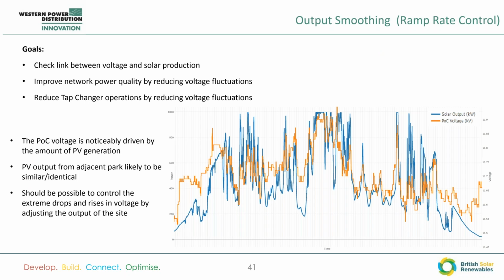Final use case, output smoothing, ramp rate control. So we found that the voltage does fluctuate in line with solar production. Again, we're assuming that the PV production from Higher Hill is likely to be very similar in terms of percentage to what it was at Copley Woods, because they're literally in the same place. So you can see here the POC voltage versus the solar output, they correlate very closely.